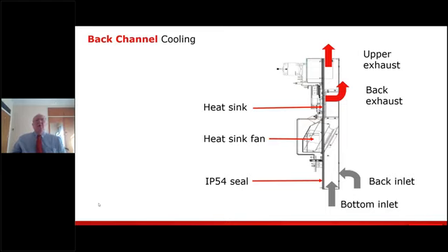Now, we wanted to take that one step further, because we said we can offer an even better solution whereby you can reduce that heat going into the actual switch room even further. So all the Danfoss drives, 90 kilowatts and upwards, incorporate what we call a back channel cooling design. This has separate cooling paths for the power components and the control electronics, and we have an IP54 seal between these two paths. This back channel cooling removes approximately 85 to 90% of the power lost directly through the heatsink, leaving only 10 to 15% of the total loss, which is then dissipated into the switch room.